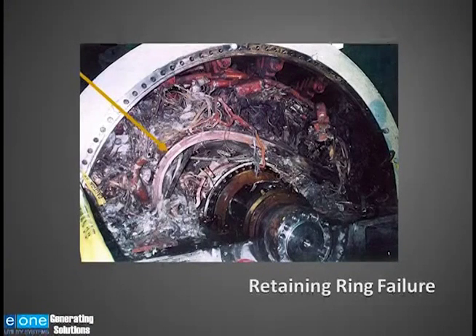This slide shows a retaining ring failure. The retaining rings are the most highly stressed mechanical components in the generator, and you need to make sure that the integrity of these rings is maintained. As I mentioned, some earlier retaining rings were made of an 18-5 stainless steel, which could get corrosion cracks as a result of moisture or high dew point. You certainly don't want this to happen to your generator.